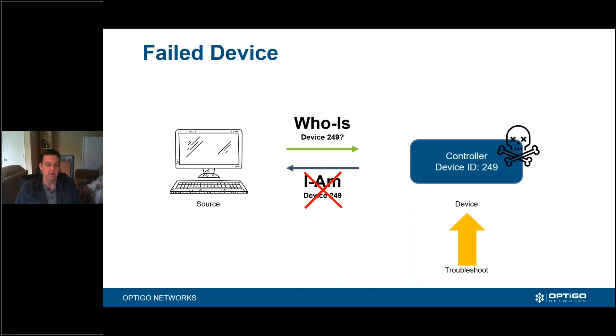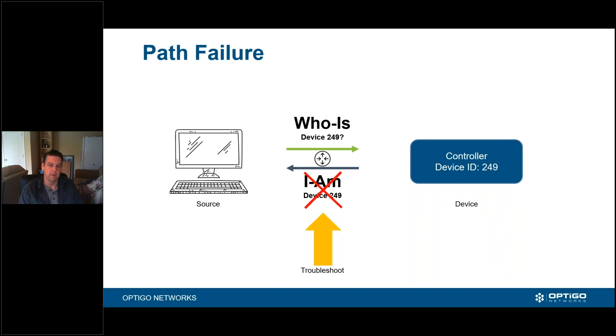There's also the other side where maybe the device is supposed to be there but it's just not answering. Assuming you've answered the question of whether the device is supposed to be on your network, and the answer is yes, then we come back and say let's go find the device — see if it's still online. Maybe it has no power, maybe the network communication cable has fallen off, maybe there's a break in the line. If the device is powered up, then it's got to be something in the communication — maybe the Ethernet wire changed, a switch failed, or an MSTP-to-IP router failed.